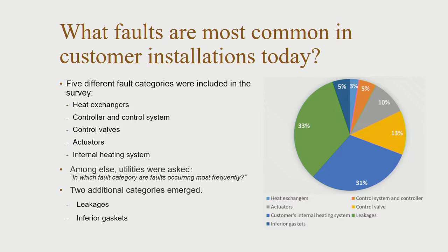This was a bit surprising to us, because a lot of literature speaks about fouling of heat exchangers as a very common fault. But since this study was conducted in a Swedish context, where we do a lot to reduce fouling, we believe that's why this fault category was so small. As mentioned before, utilities don't really gain access to internal heating systems, and as you can see, many faults occur in these systems. So it might be very important to develop analysis tools that can identify these faults in future systems.